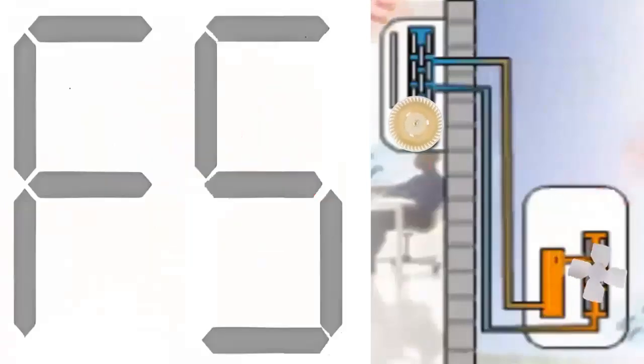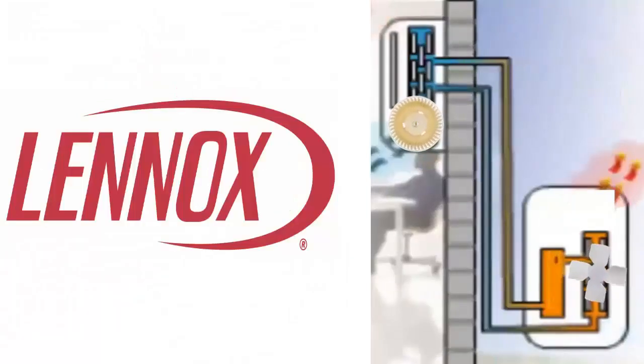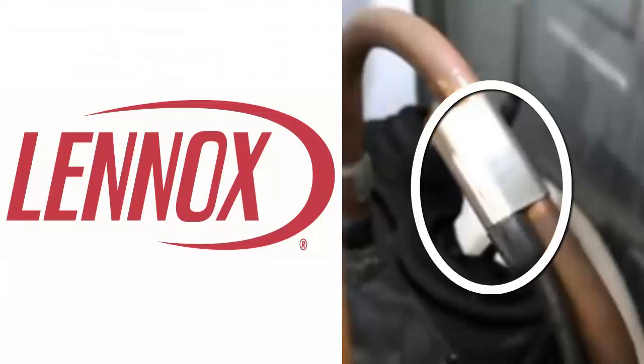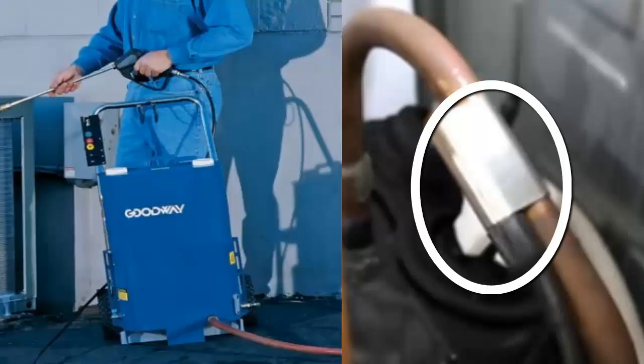Code F5 indicates a problem with the refrigerant discharge temperature sensor at the compressor outlet. This sensor is located on the thinner pipe of the compressor in the outdoor unit. If the issue is an actual discharge temperature much higher than normal, it is recommended to check the correct rotation of the outdoor unit fan, eliminate refrigerant overcharge, and check the cleanliness of the outdoor coil.